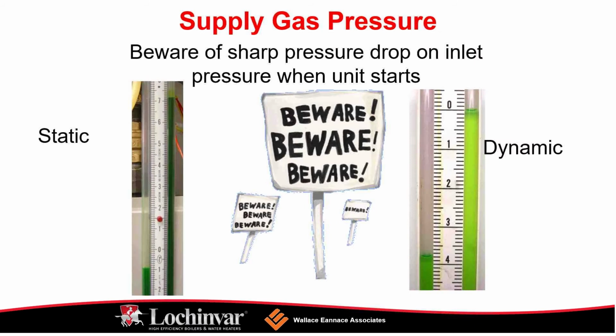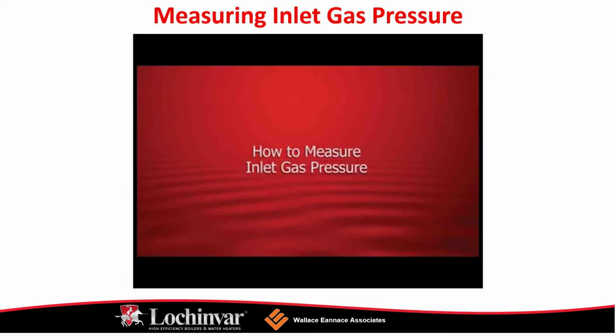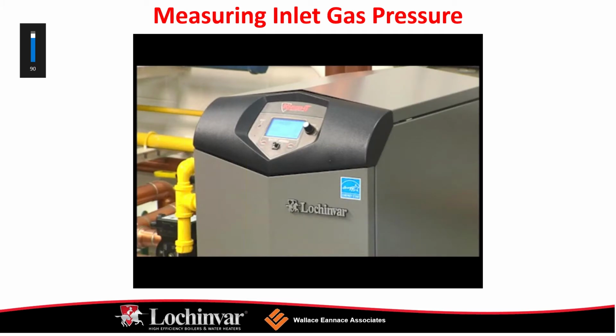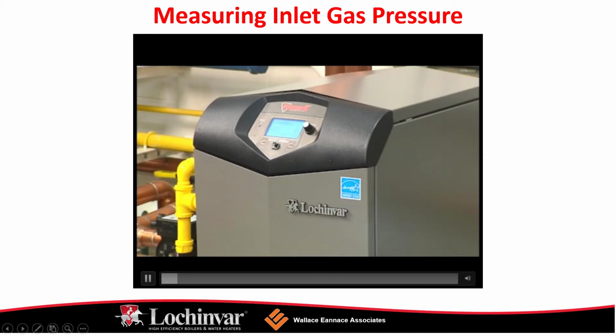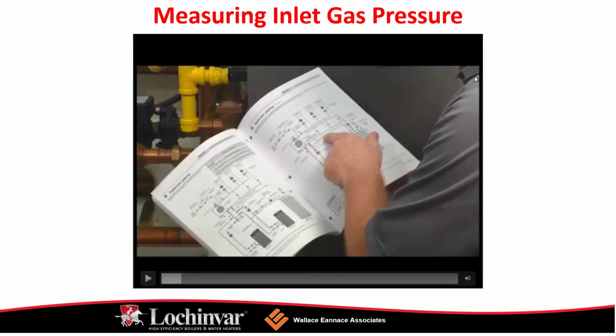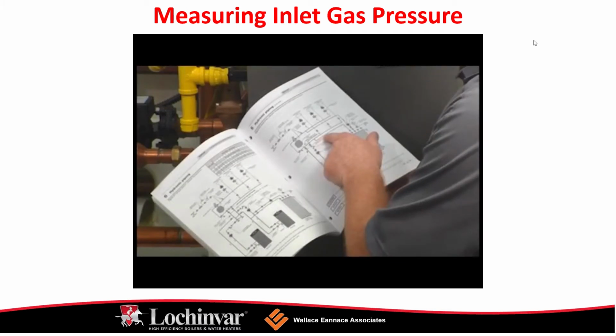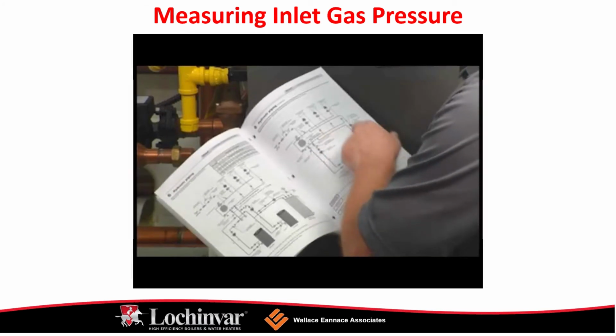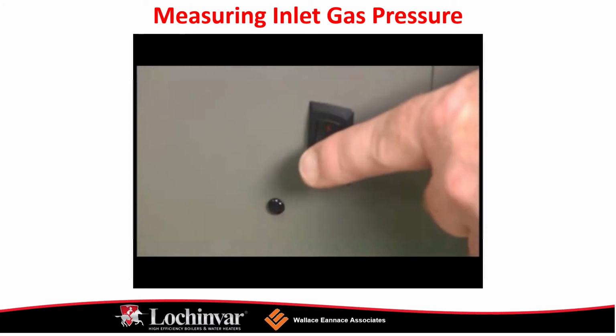Touch on some gas here and the gas supply requirements. 51 to 211 models have a half-inch connection. 286 models, and these numbers might have slightly changed, have a 3/4 inch connection. 400 to 801 models have a 1 inch NPT connection. So gas lines must be sized as per the National Fuel Gas Code line sizing tables. Also take note, when installing flexible gas lines, ensure that the line has an adequate capacity to allow the boiler to fire at full input. Very important.